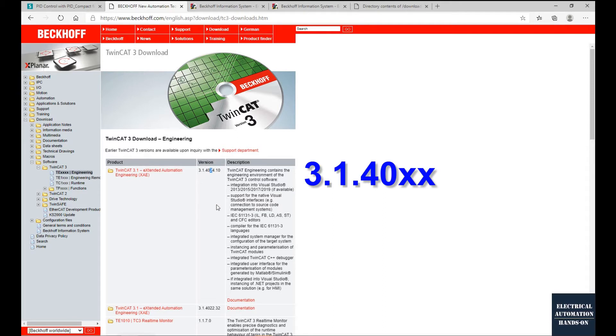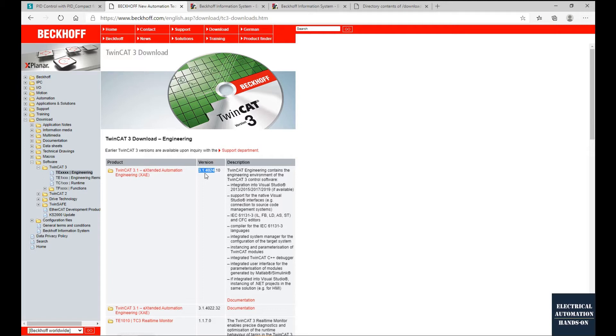The revision version for the software and hardware must be the same. For example, this is version 3.1 4024 — the hardware and software must match. This is a similar idea to Rockwell Allen-Bradley: their main version must be the same. If the hardware is version 31, you have to install Studio 5000 version 31 to program the controller or upload the program from the PLC.